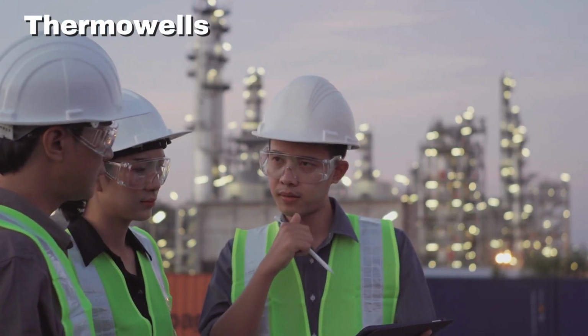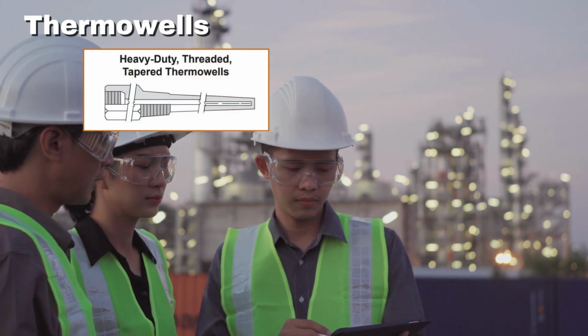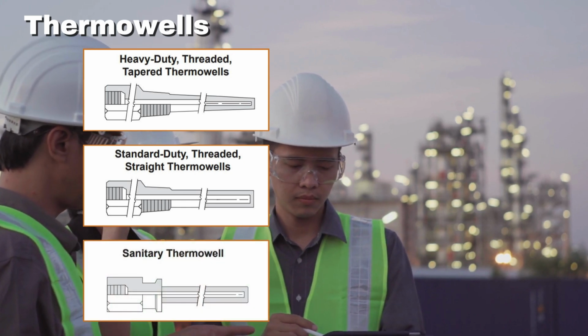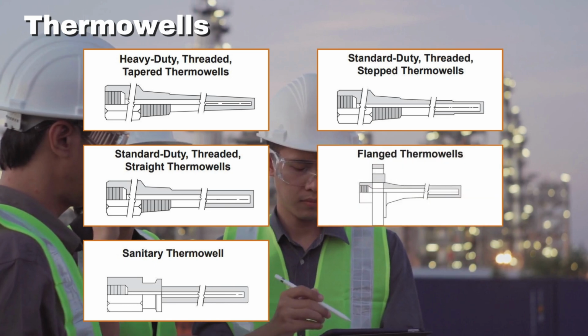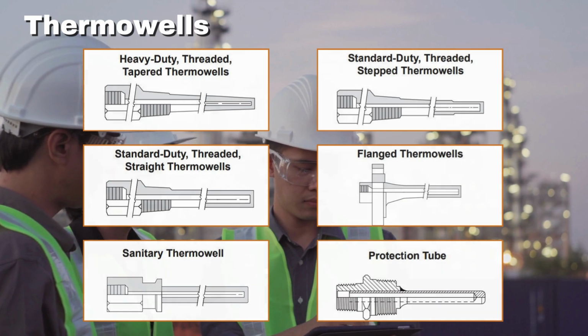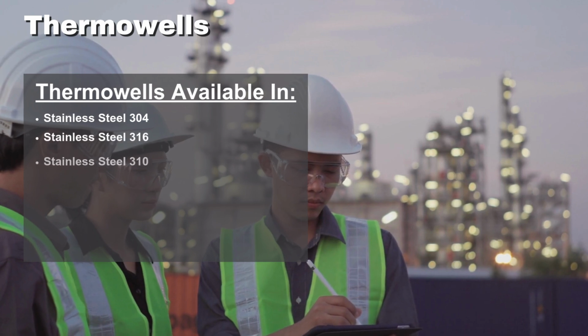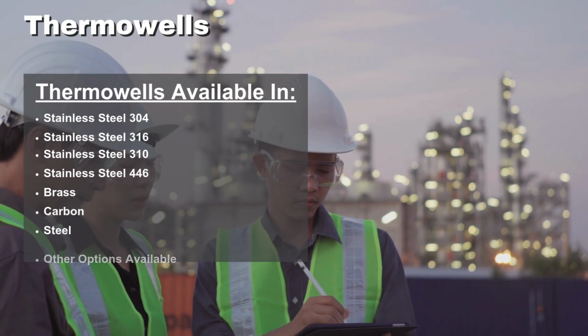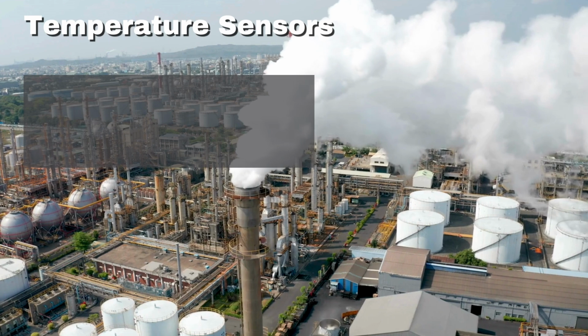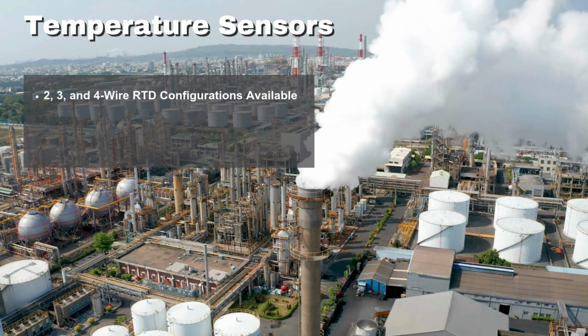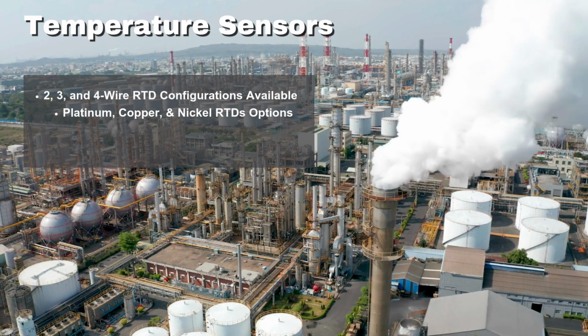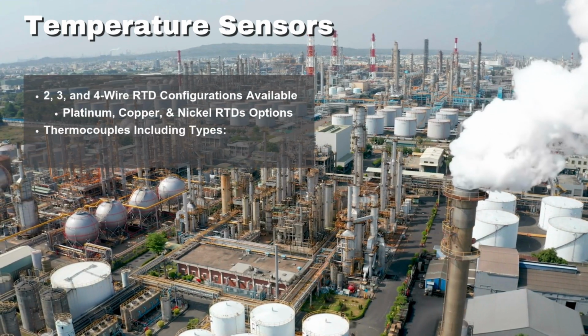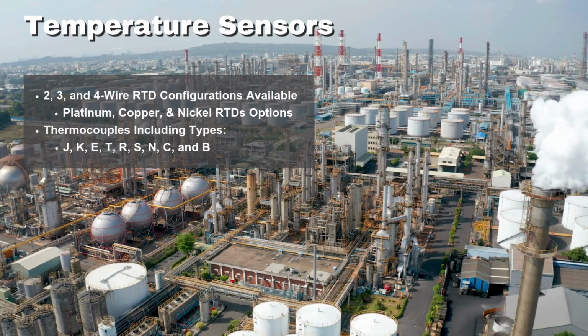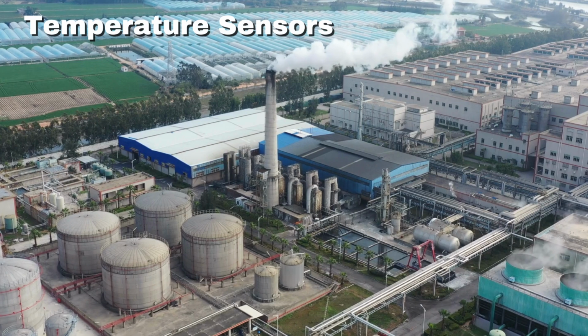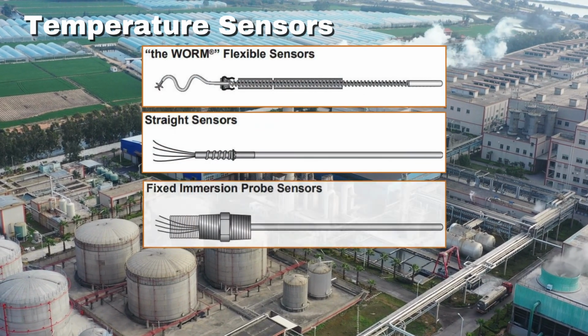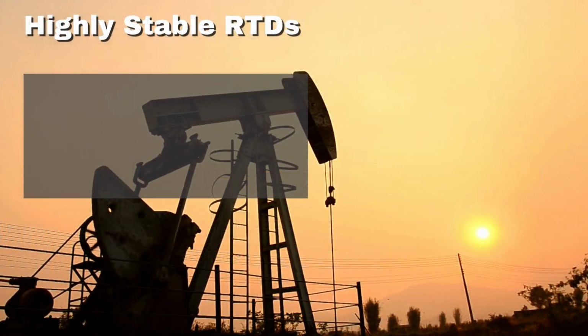We also offer a wide range of Thermowells to meet any process requirement, including heavy-duty threaded tapered Thermowells, standard-duty threaded straight Thermowells, sanitary Thermowells, standard-duty threaded stepped Thermowells, flange Thermowells, and protection tubes. These are available in materials such as stainless steel 304, 316, 310, 446, as well as brass, carbon steel, and other options. Our temperature sensors provide extensive versatility, including RTDs available in 2, 3, and 4 wire configurations with options for platinum, copper, and nickel RTDs. Thermocouples, including types J, K, E, T, R, S, N, C, and B. We also offer specialized designs like the worm flexible sensors, straight sensors, fixed immersion probe sensors, and sanitary sensors.